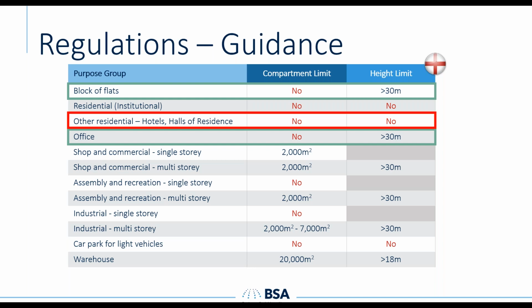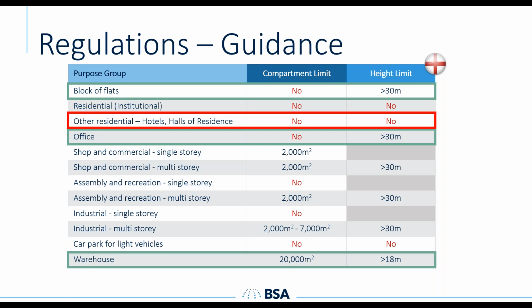For industrial and commercial buildings, warehouses with compartments larger than 20,000 square meters, or a building higher than 18 meters, would attract sprinkler guidance in England. To put that in context, that's the size of 3 football pitches or a 6-story building.